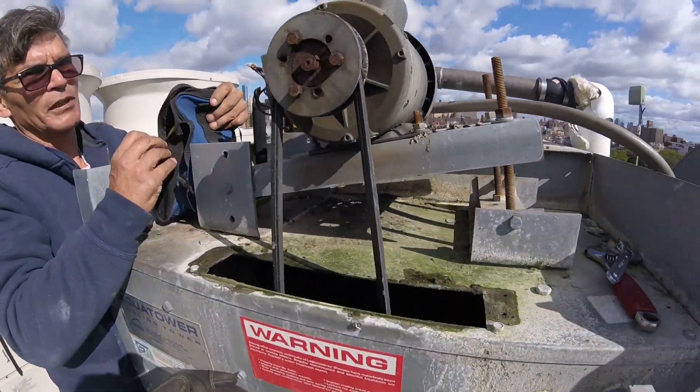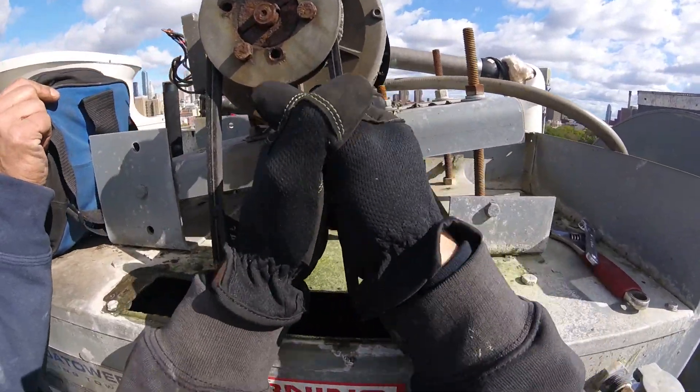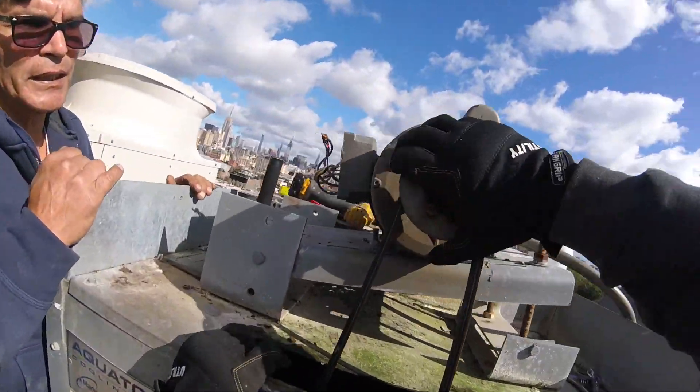This is rock solid. It's a hub type. Trying to pull down the belt — this thing is solid, can't even get it out. I'm going to have to cut this belt out and we're going to be replacing this motor.